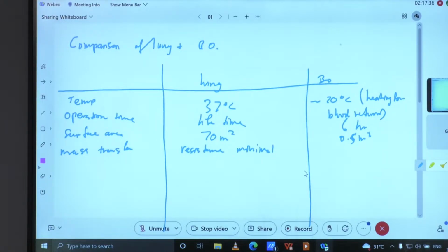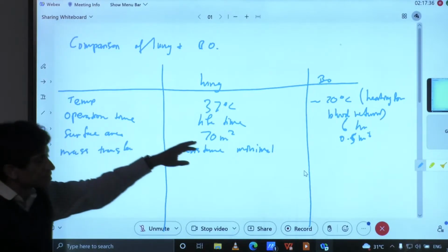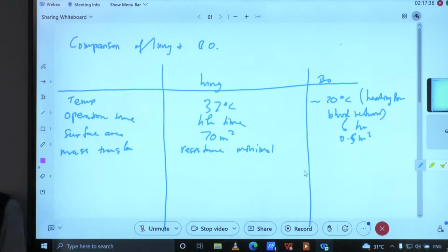Another important thing is that we are trying to minimize the priming volume, right? I mentioned that in the blood oxygenator. In the lungs, you're not trying to do that. You have a huge surface area, 70 square meters actually, because this is all a part of your body. It's biocompatible. So the priming volume, if you like, of the lungs is quite high. And that's fine, okay? But for a blood oxygenator, you're adding an extra volume, so we want to keep it as small as possible. We also have to be careful about sterility in a blood oxygenator. So again, it needs to be compact.